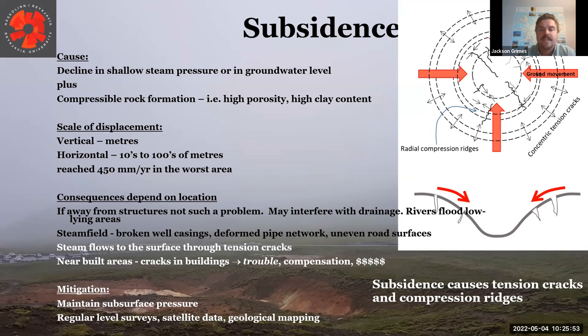And the consequences of this is it can interfere with the system itself. Rivers flood, the steam fields can change in nature, causing broken wells, well casings, or deforming the piping network. The steam can flow through the surface through these new cracks. And in general, this type of environmental effect causes large trouble for the geothermal plant.